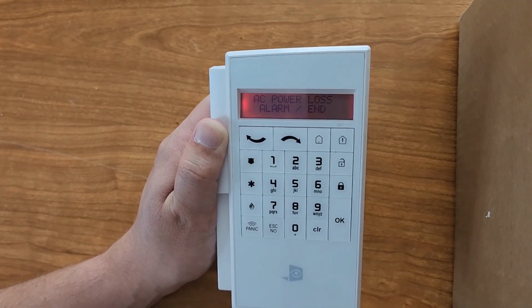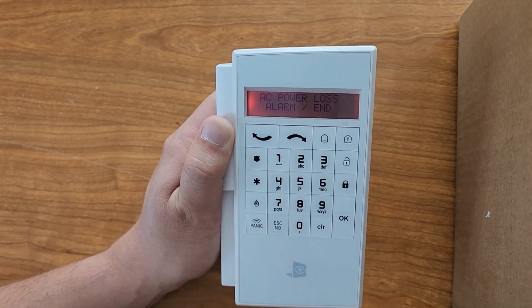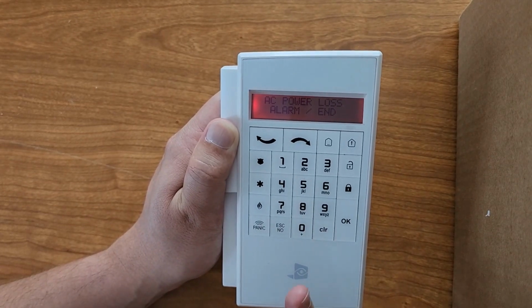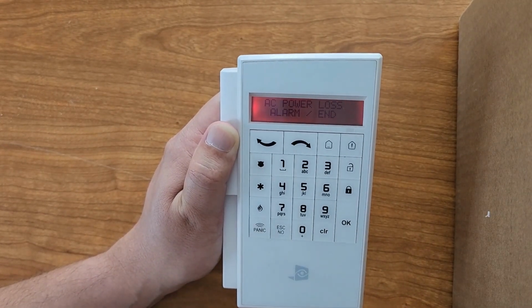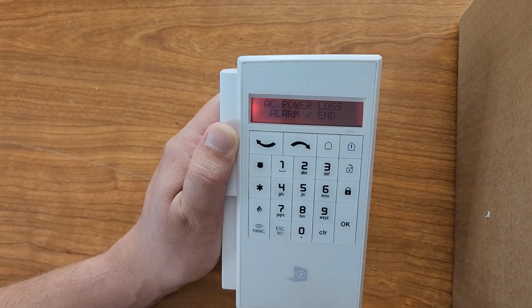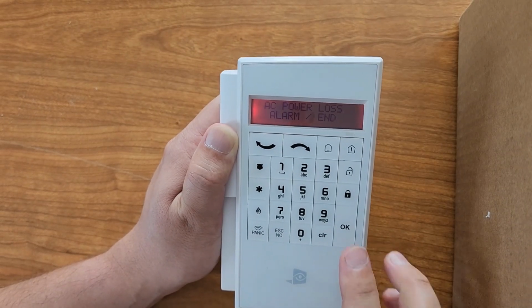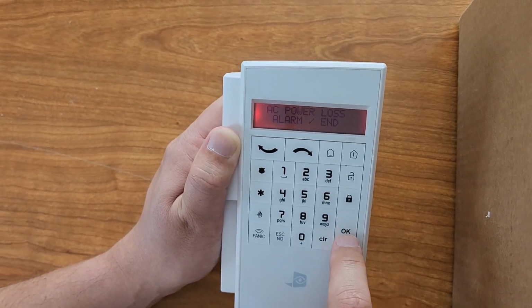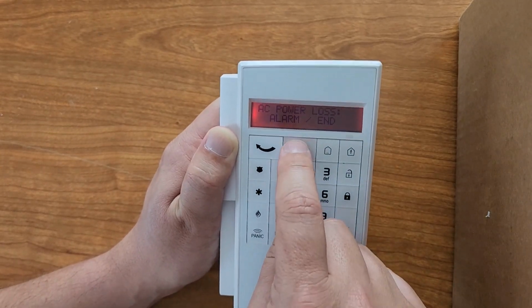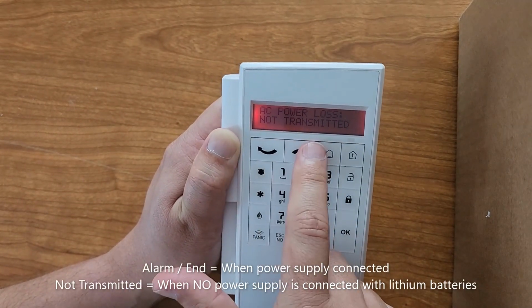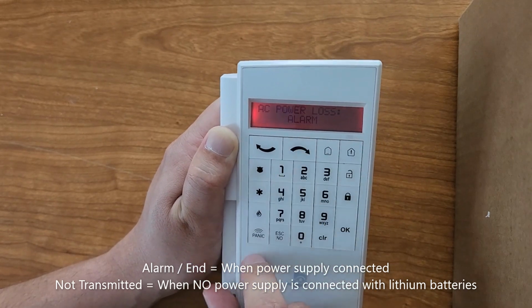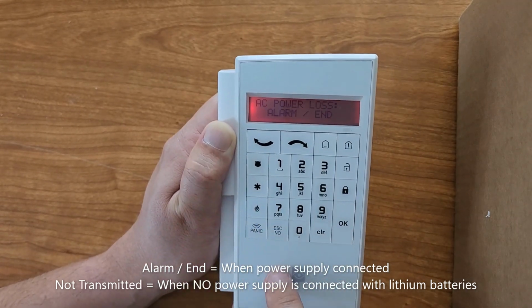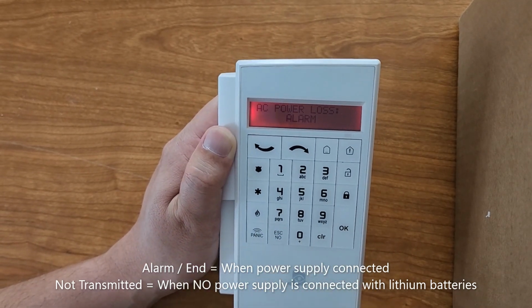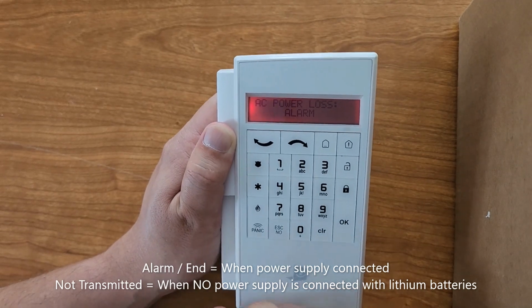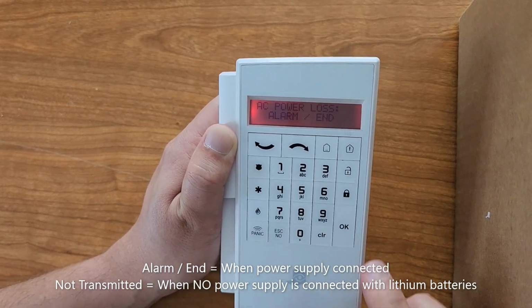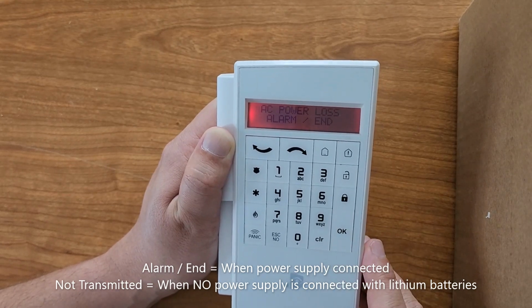AC power loss. Now my panel does not have AC power connected. It's a lithium only. But if you do connect a power supply, please leave the alarm/end so that when the power goes off, you want the power restore signal to come through as well. My panel I'm going to disable. Options is not transmitted, alarm, alarm/end. Should I leave it on alarm, then I will only get an AC fail, I'll never get an AC restore. So I want an AC restore and we'll leave it at alarm/end.